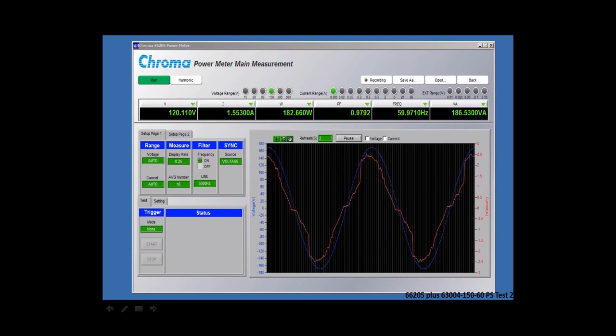to select any one of those 22 measurements to display it. But you can also record all this data to a text file, and you can record all 22 measurements simultaneously. From this screen, you can also do some range selections. You can also do various measurement display functions for averaging or for display rate. You can also do filtering if your measurement allows for filtering. We have the internal filter for 5,500 hertz. And we can also do sync voltage and sync current. This determines which measurement you're synchronized to when you're doing your measurements. Also has some test measurement capability for go, no-go, and pass-fail data.